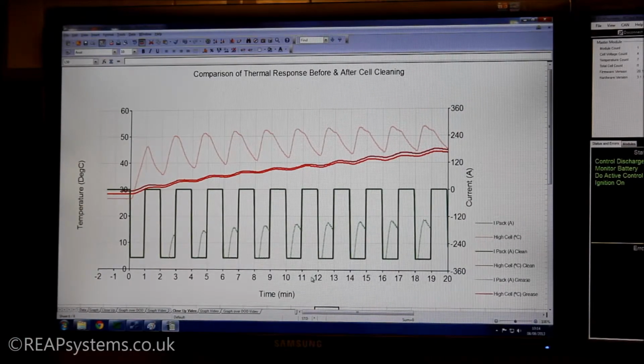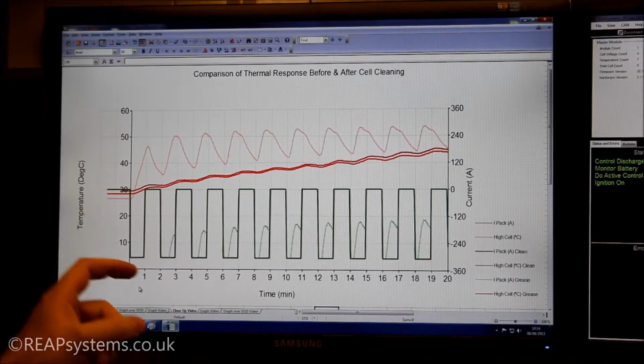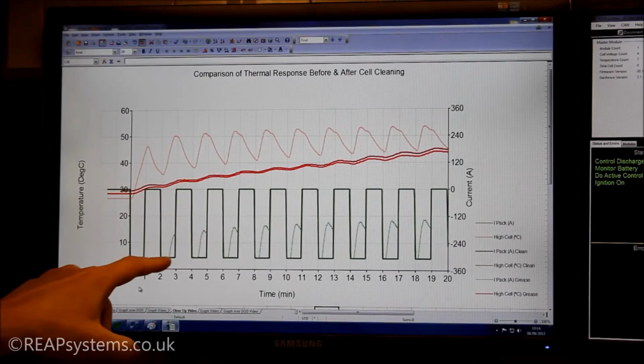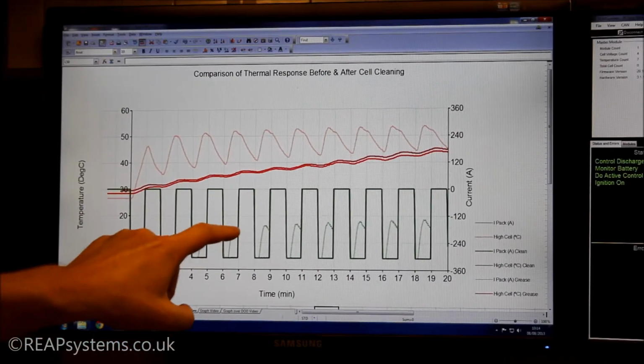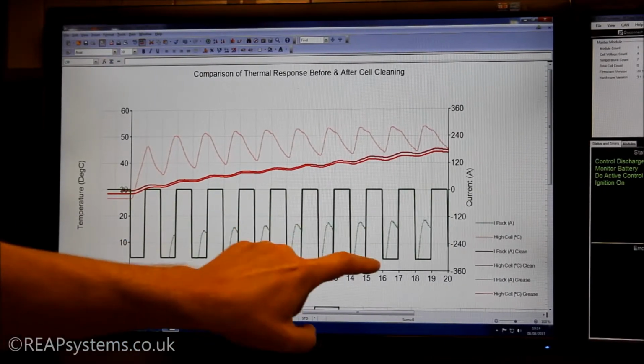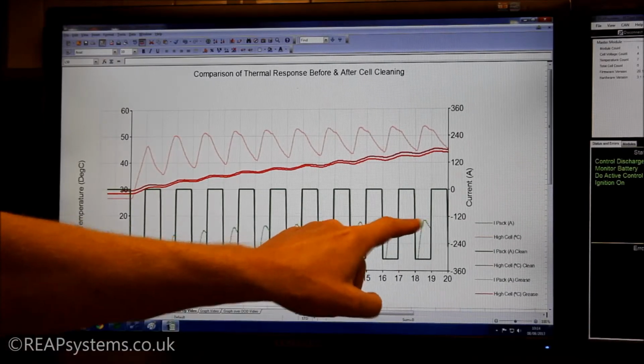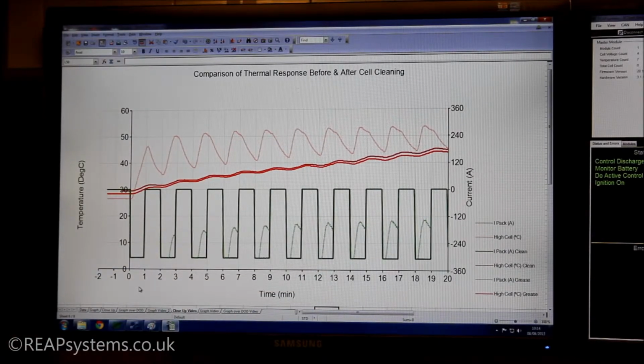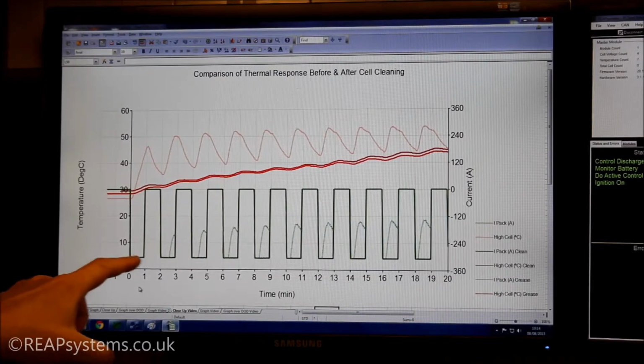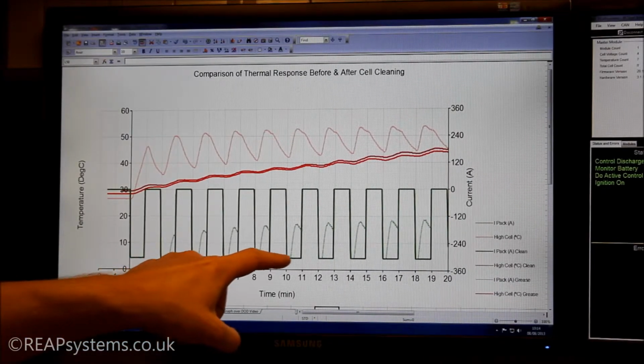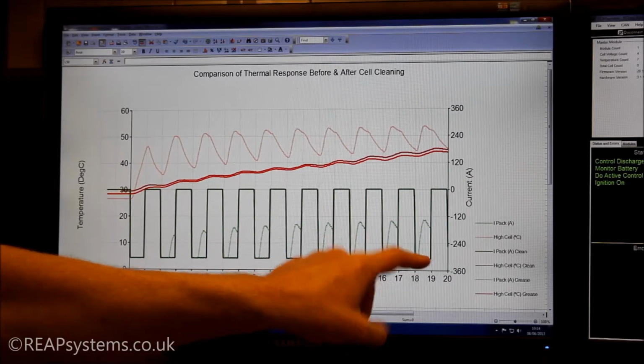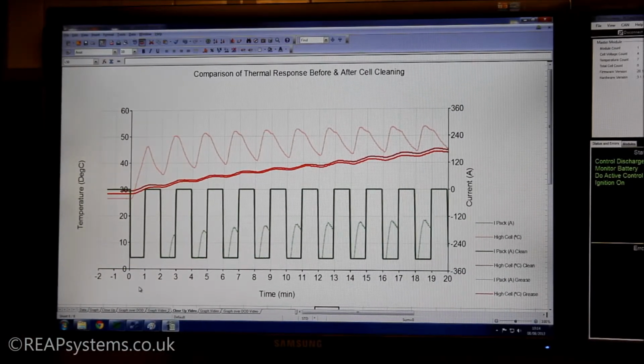So here we're showing the first 10 steps of our discharge. So we have 100 seconds of 300 amps. And what we see immediately is that the pack, which is uncleaned, has almost immediate limitation in discharge current. So this is the dotted curve here, limitation in discharge currents. Whereas if you have a module which has been cleaned and greased, we're able to pull our full 300 amps for 60 seconds for the first 10 cycles. And this actually corresponds to half of the battery capacity being discharged.